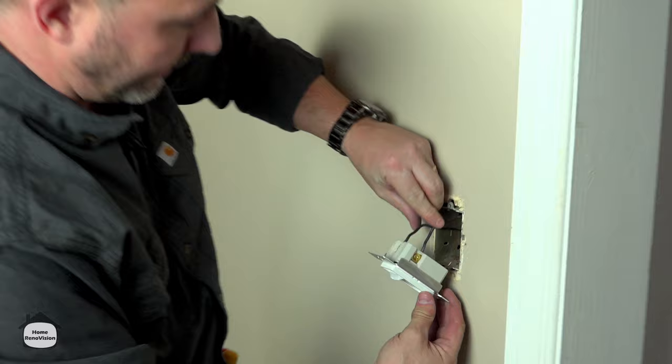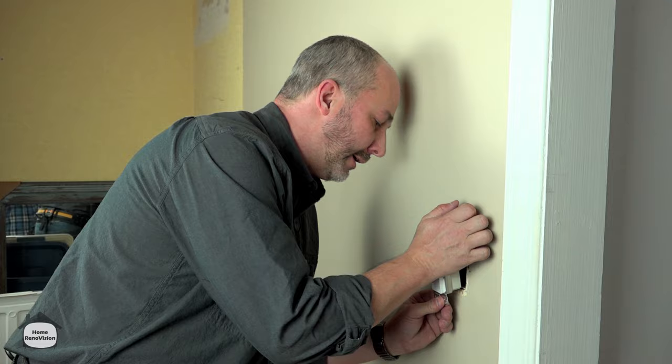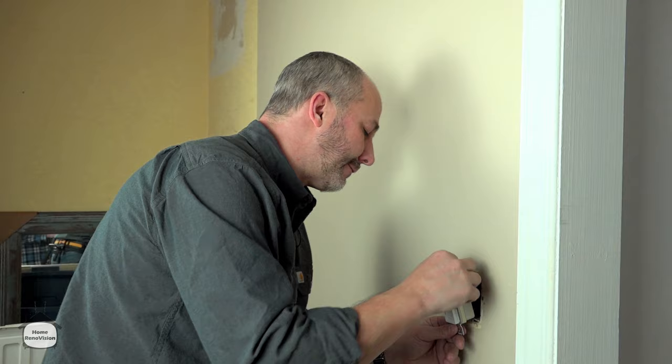That's it. Now when you're putting your wires back into a box you want to pinch them so they're in an S-curve. You want them to have that flexibility so that when you push it back you have an S-curve that's going to collapse, sort of bend up and down. If you just have it straight out and you push, they'll buckle out the sides and make all kinds of mess. This is perfect.